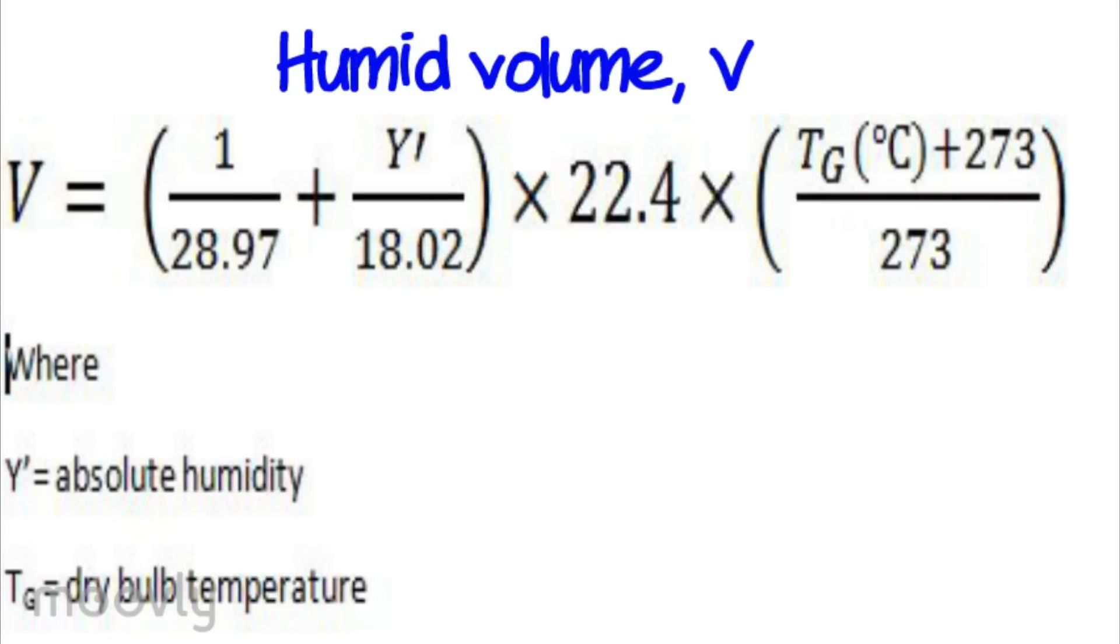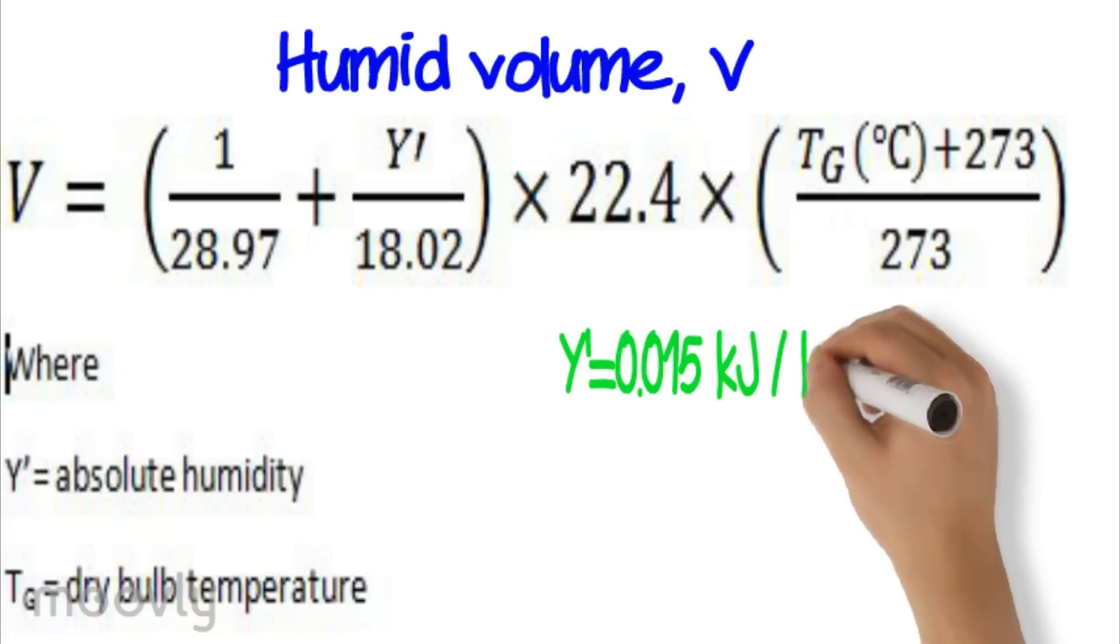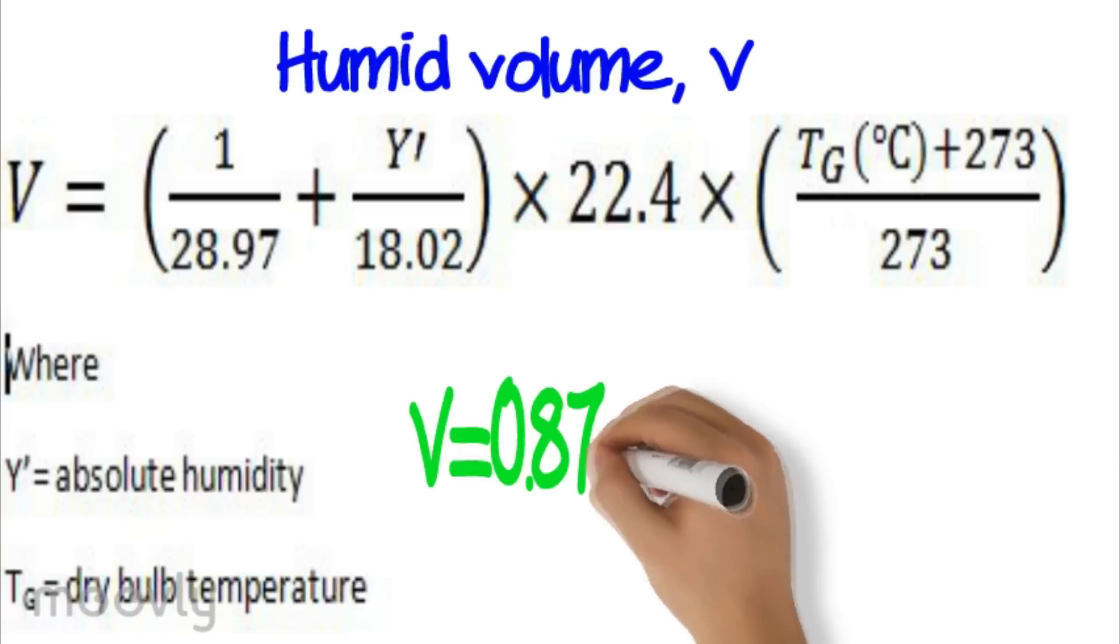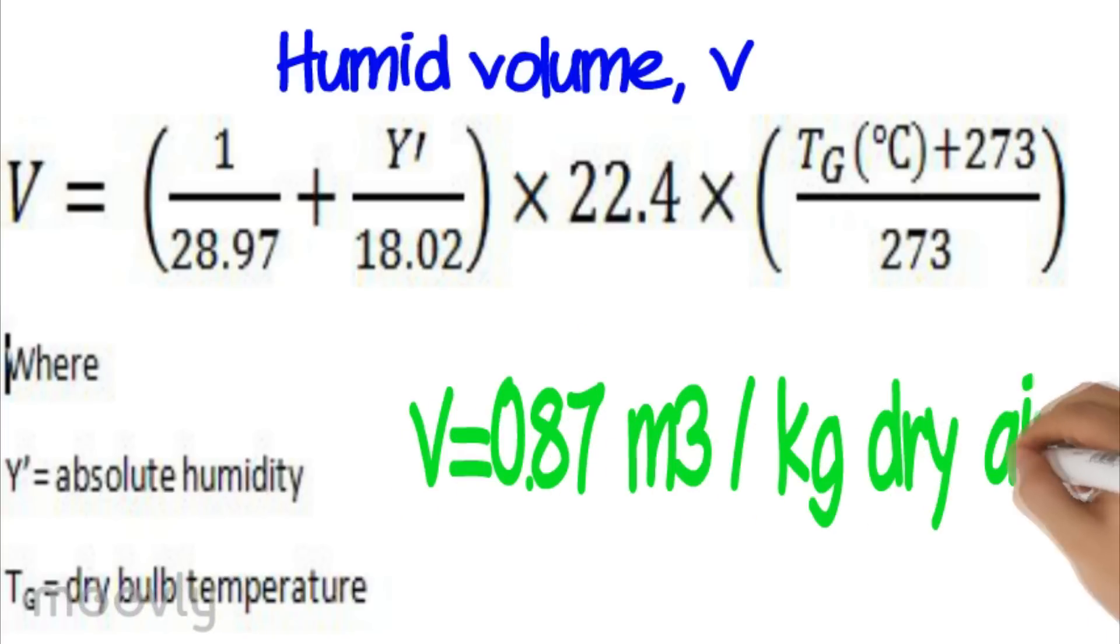Humid volume can be found using the formula by substituting absolute humidity of 0.015 kg per kg and dry bulb temperature of 27 degrees Celsius. Humid volume is 0.87 cubic meters per kg dry air.